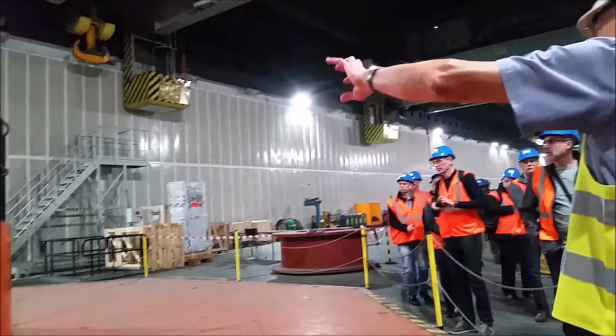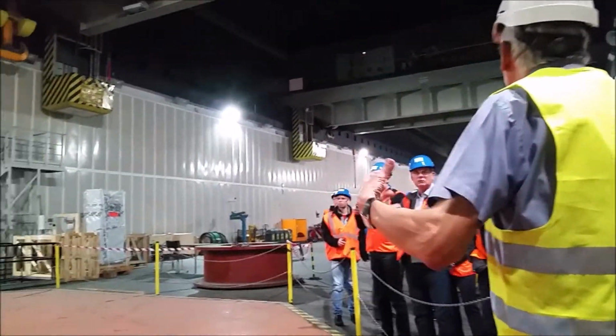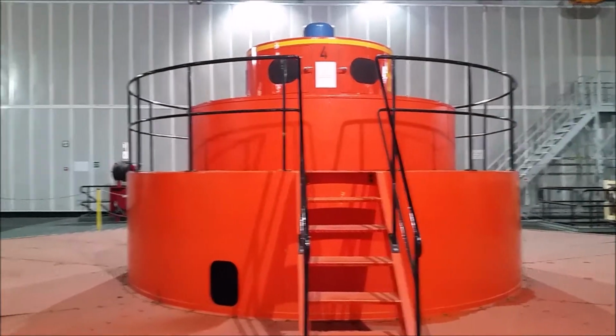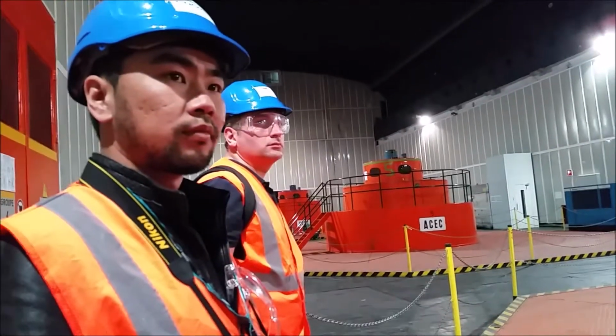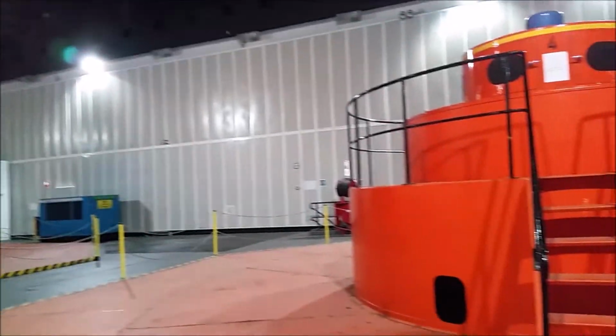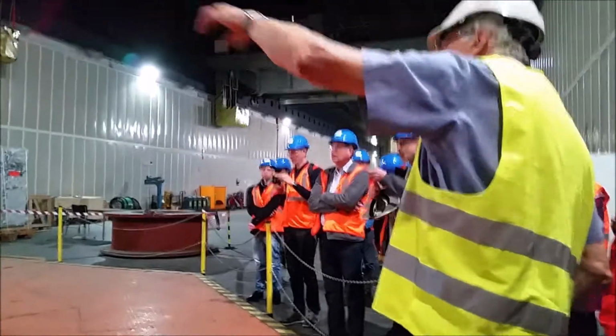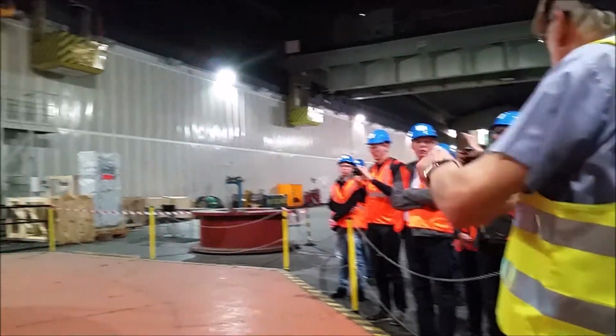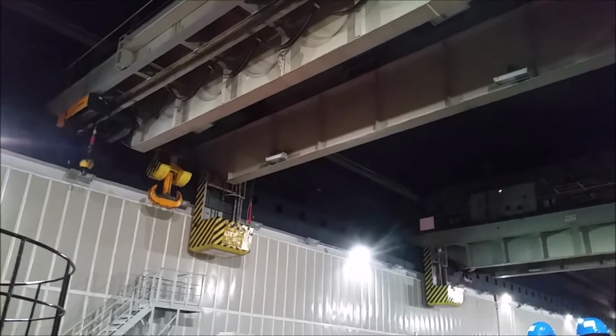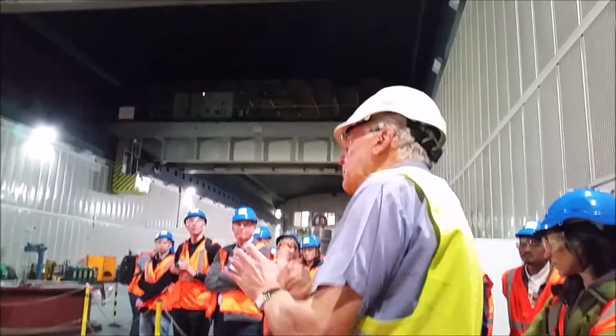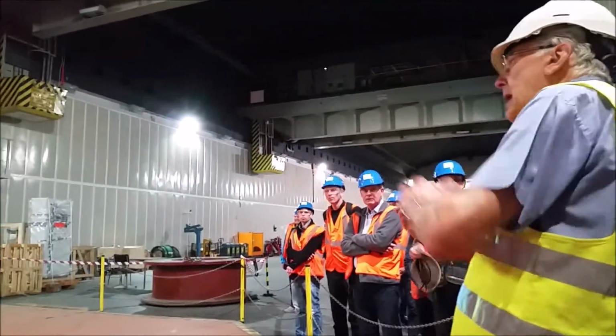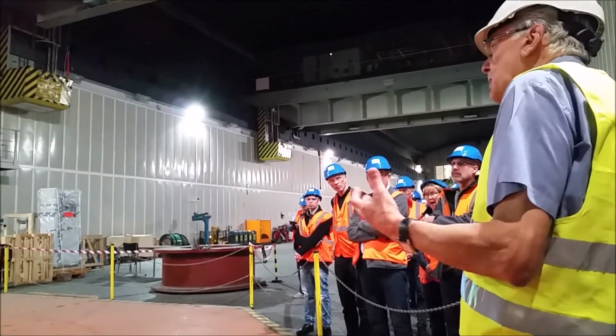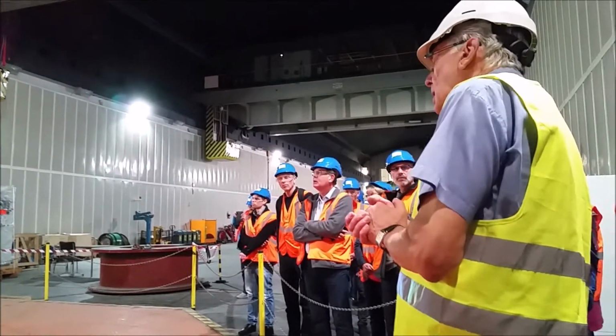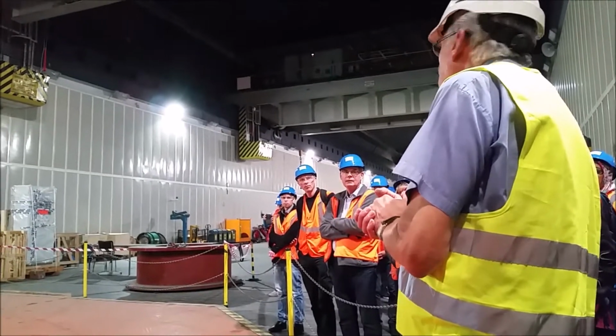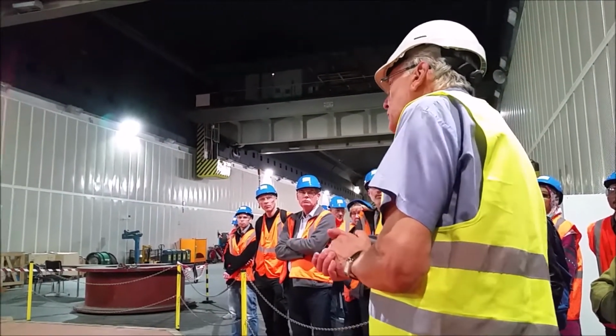Because all of this is installed vertically, under the first and the second cover we have the starting motor, which is an asynchronous starting motor. An asynchronous starting motor has a much higher torque than a synchronous motor. A synchronous motor, you don't know in which direction it will start. Under the first cover is the commutator and brush system, because if you have to bring voltage and power to the rotating part, you can do it with a brush commutator system. On the top, the blue cover is a tachymeter, to measure the frequency. The rotation is 300 rotations per minute, and always the 50 Hz of the production starts from here.